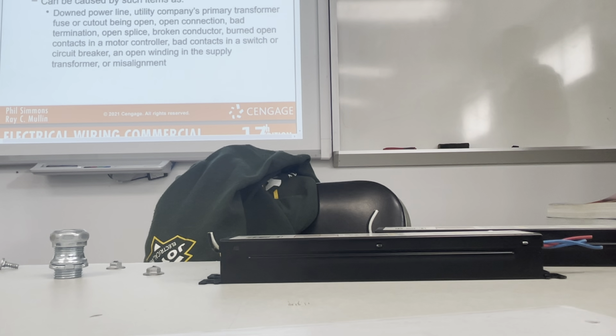Single phasing means one phase is open somewhere. It can be caused by such items as a down power line, a utility company's primary transformer fuse cutout being open, an open connection, bad termination, open splice, broken conductor, burned open contacts in the motor controller, bad contacts in a switch or circuit breaker, an open winding in the supply transformer, or a misalignment. Whew, boy, that can be caused by a lot of things, huh? Good thing we're electricians, good thing we can do some troubleshooting, good thing we can figure all this out.